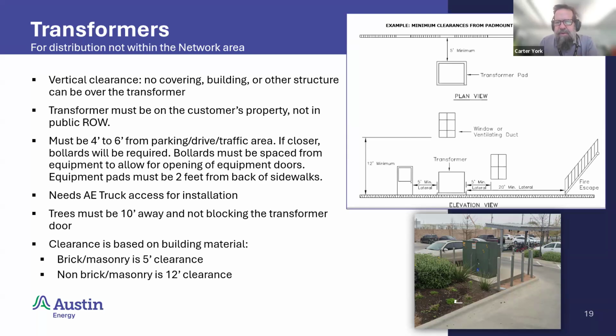There are different clearances that are required around transformers. On the top, the plan view, so we're looking at a transformer from above. We see the transformer pad. The long line across the top is a wall, and we see fire escape stairs to the right. If this wall is constructed of brick or masonry, the minimum clearance to that wall from the transformer pad is 5 feet. If it is not made of brick or masonry, then it is a minimum clearance of 12 feet to that pad. In the bottom of that image, the elevation view, now we're standing out in front of the transformer, looking at it in front of the wall.